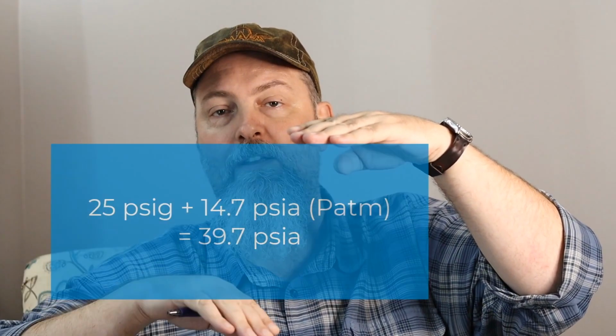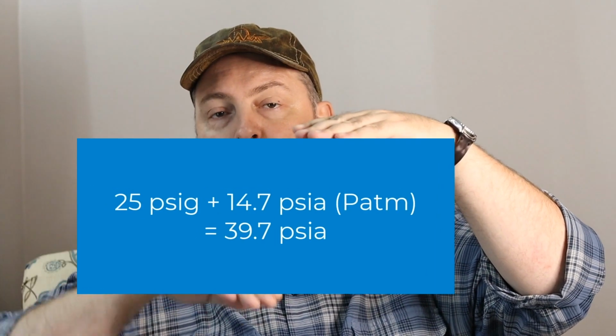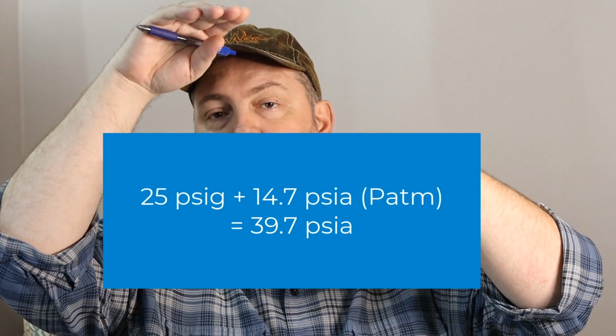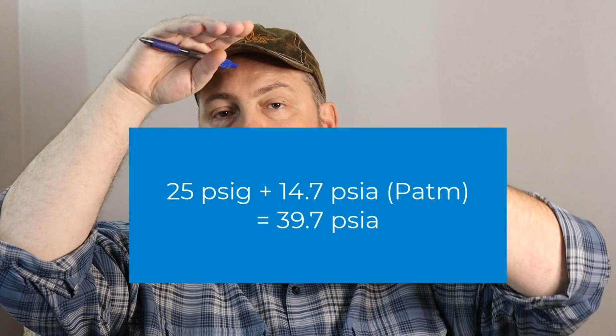So 25 pounds gauge, up here, above the relative 0 of atmospheric pressure, we add 14.7 to that 25 pounds, and now we have the absolute pressure, the PSIA, of 39.7 PSIA.